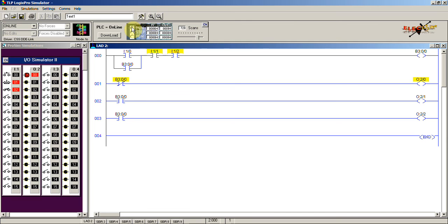After keeping the PLC in run mode, we will start the motor, and once we press this start push button, our motor starts rotating. Here I'll press the start push button. It is momentarily pressed and released. Now the logical continuity is provided in this path. Since this motor is turned on, you can see that this output, this yellow indication, is that the motor coil is energized, and this green pilot lamp shows that the motor is running.